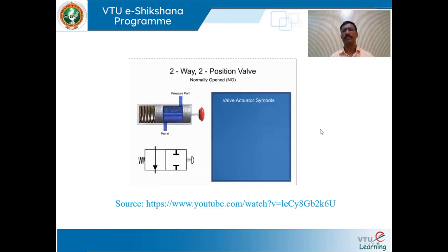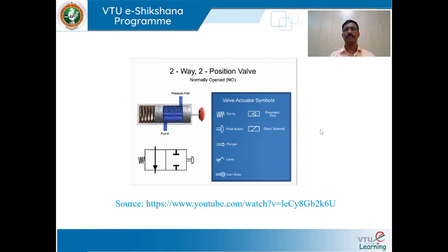Mechanical actuators change valve positions with springs, push buttons, plungers, levers, and cam rollers. Pneumatic pilots change valve position with a pressurized air signal. Electric solenoids that directly move the valve element are called direct solenoids; those that open small pilot valves allowing pressurized air to move the valve element are called solenoid controlled pilot operators.